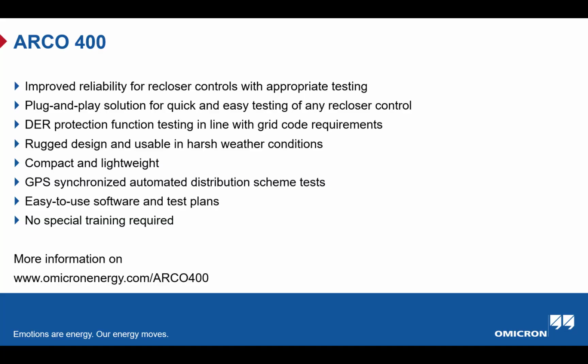Finally, let's summarize the key benefits of the ARCO 400. With proper testing, it improves the reliability of Recloser controls and ensures correct operation in the field. The plug-and-play approach makes testing quick and easy without the need for complex wiring or setup. It also supports DER protection testing, helping you to meet modern grid code requirements. The device is rugged and designed for outdoor use, so it performs well even in harsh conditions. At the same time, it's compact and lightweight, making it easy to carry and use on site. With GPS synchronization, it also enables advanced testing of distribution automation schemes. And with user-friendly software and predefined test plans, testing becomes simple and efficient with no special training required.